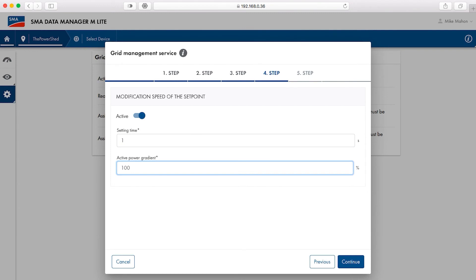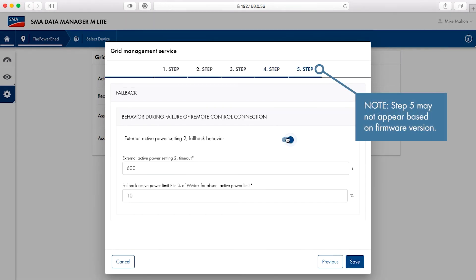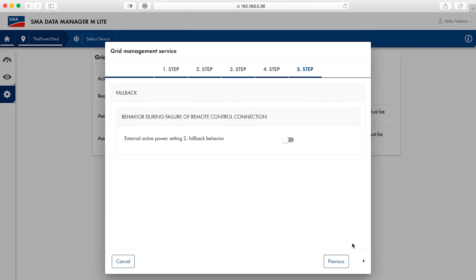This allows for up to 100% of the total power to be limited in one second if the load demand drops dramatically. It is the responsibility of the system operator to correctly set these values. In step five, if needed, select the slider next to external active power setting 2, fallback behavior. Select values for timeout and fallback active power limit. Click save when done.